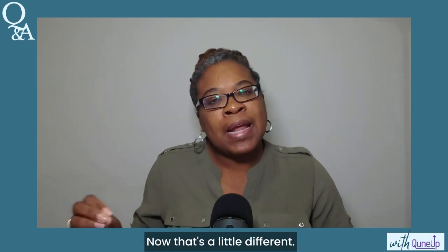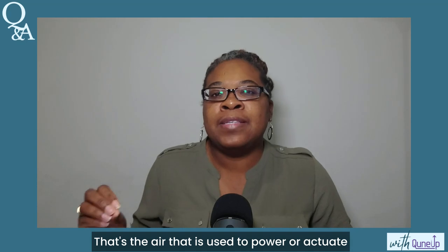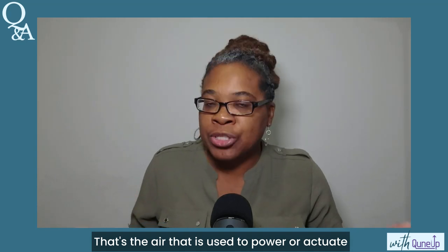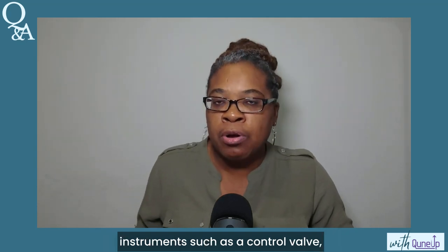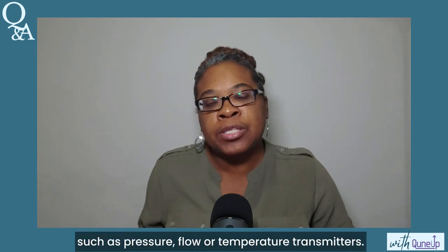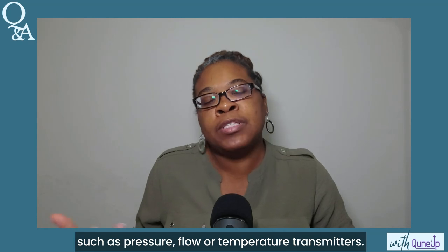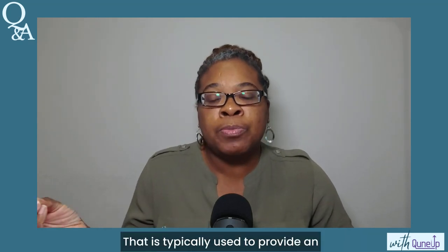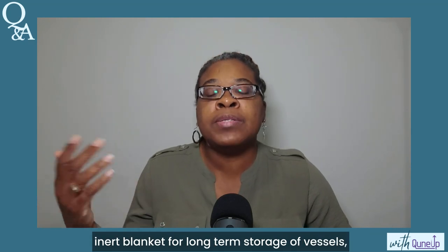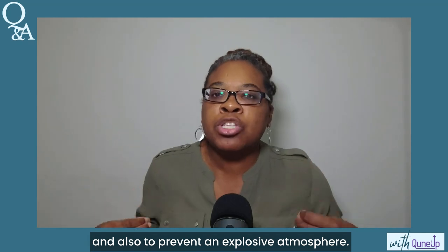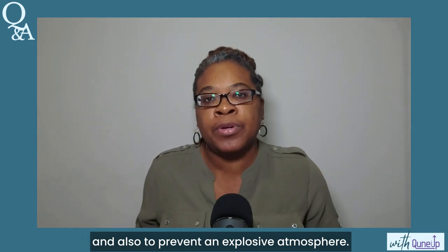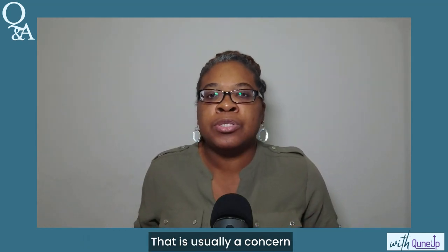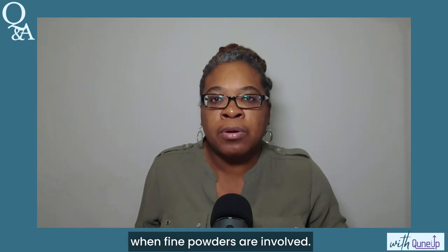Instrument air. Now, that's a little different. That's the air that is used to power or actuate instruments such as a control valve, as well as instruments such as pressure or flow or temperature transmitters. Nitrogen, that is typically used to provide an inert blanket for long term storage of vessels and also to prevent an explosive atmosphere. That is usually a concern when fine powders are involved.